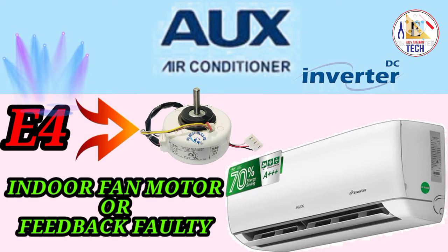You have to check the connection and wire between the indoor PCB and the fan motor to see if it is correct or not. If it is not correct, correct it properly and start the unit. And if it works normally, it means it was due to a wire cut or damage to the wire. If you get the error again, then you have to check the out supply of your indoor PCB to see if it is good or not. If the out supply is good, then you have to change the fan motor and you will get the solution for the error E4.